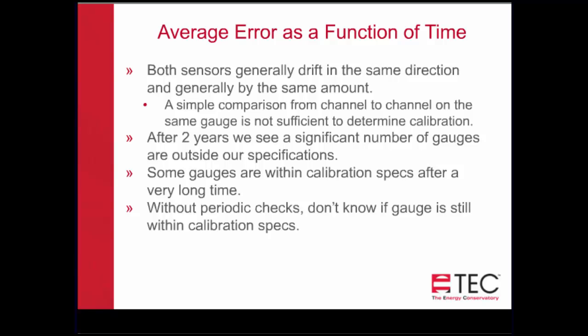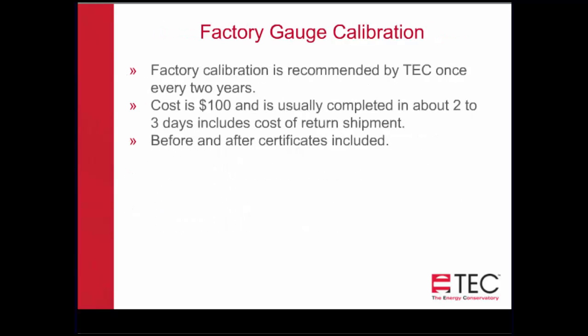After 2 years, we do see a significant number of gauges that are outside of our specification. And certainly there are some gauges that are within specs at a very long period. When you look at that graph, there are gauges that have been out there for 4, 5, 6 years and will still meet that accuracy of 1%. The difficulty is we never know which gauge that is. So it's always a wise choice to do the periodic check to see where your gauge is. And if you're able to compare that to a recently calibrated gauge, that's the best standard. Paul will talk about all those procedures next.